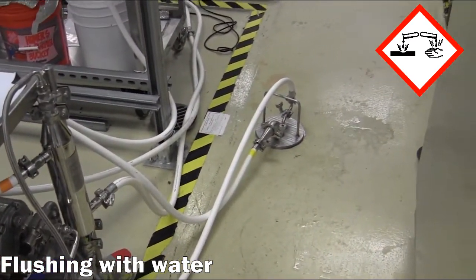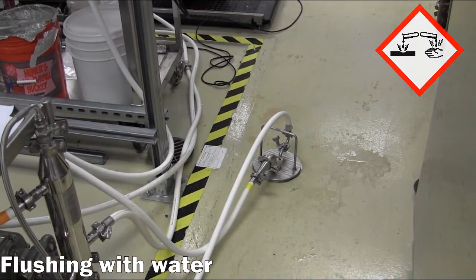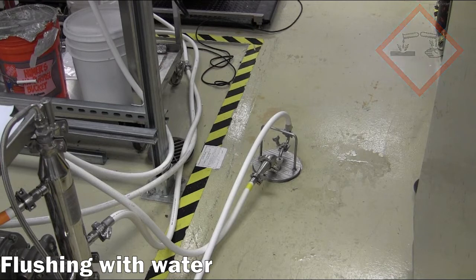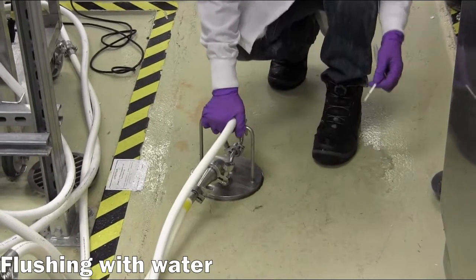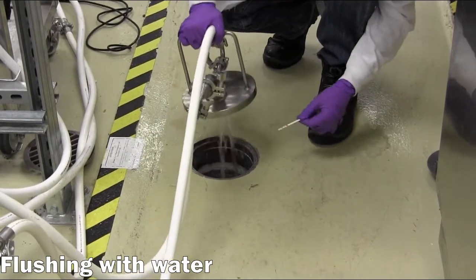The caustic solution will be gradually flushed out until a neutral pH is reached on the permeate outlet stream, as measured with a pH test strip or pH meter.